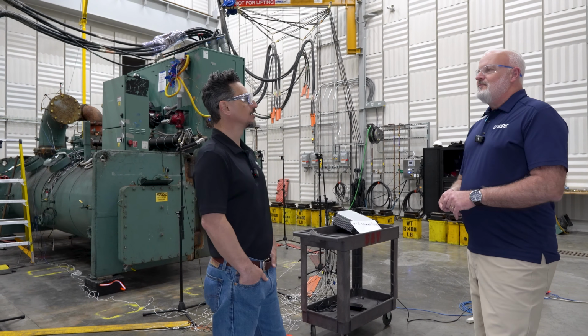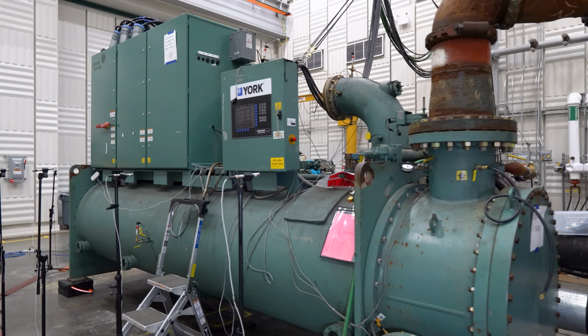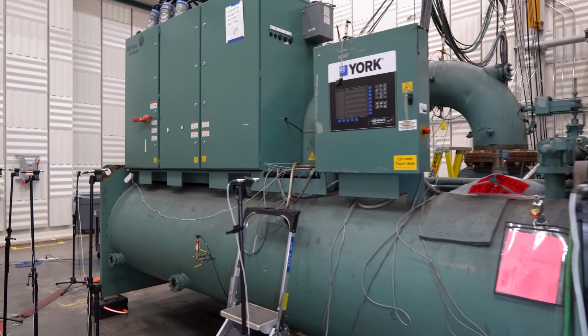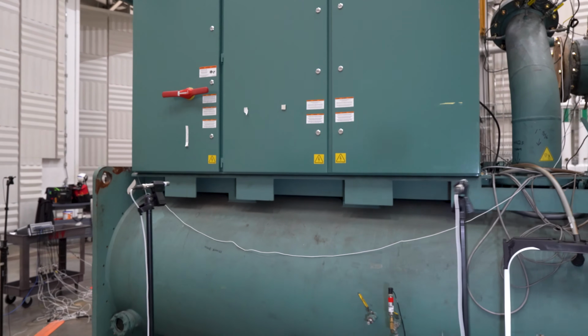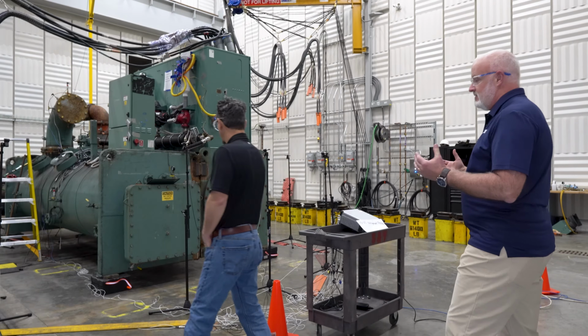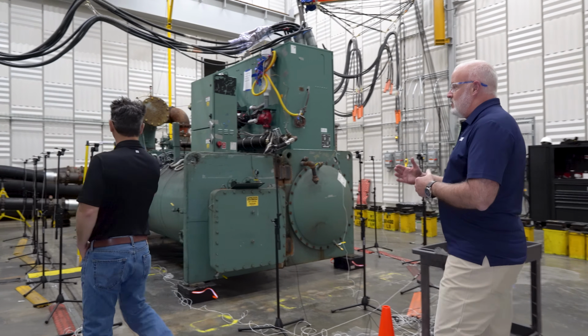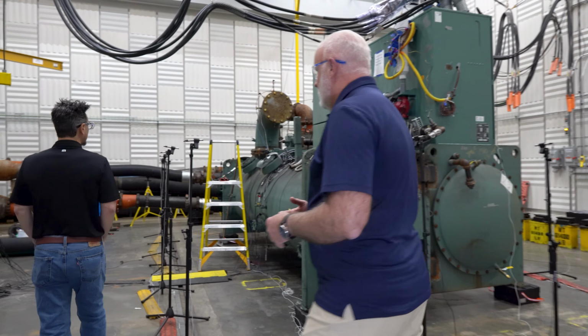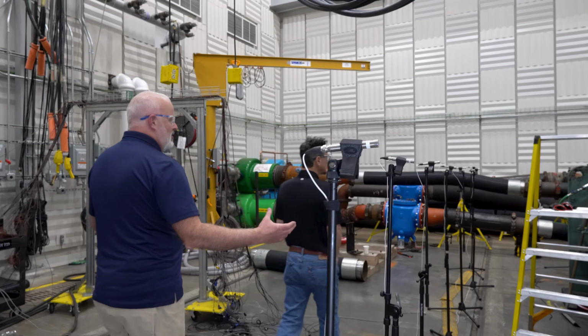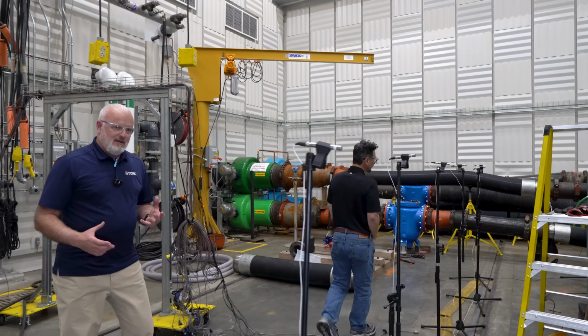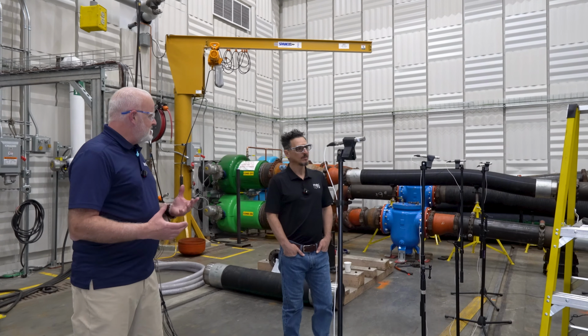And the purposes are? Our purpose is to measure sound from, in this case, a water-cooled chiller. So we've got a centrifugal behind us, an example of a bunch of microphones. One of many, right? And you can see those microphones are set at a prescribed distance, because our measurements of sound have to follow industry standards, right?